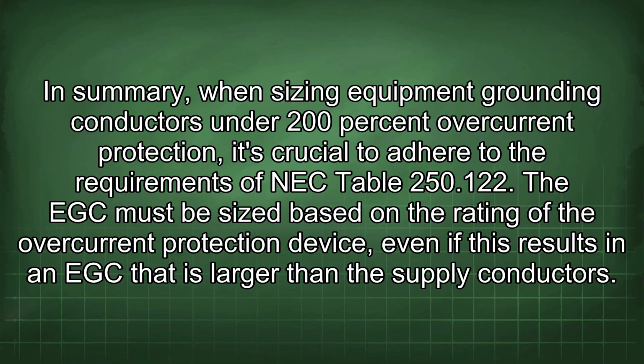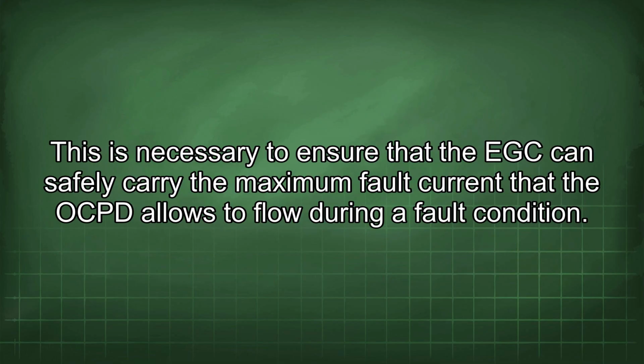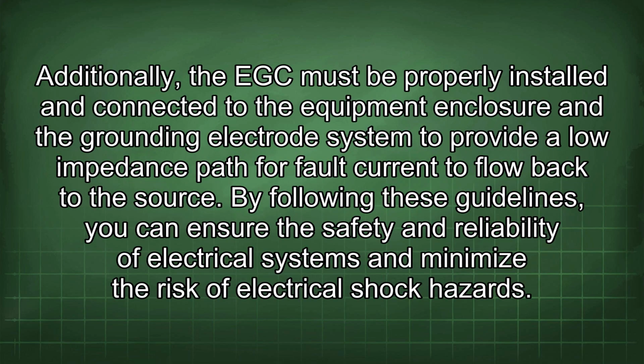In summary, when sizing equipment grounding conductors under 200% overcurrent protection, it's crucial to adhere to the requirements of NEC Table 250.122. The EGC must be sized based on the rating of the overcurrent protection device, even if this results in an EGC that is larger than the supply conductors. This is necessary to ensure that the EGC can safely carry the maximum fault current that the OCPD allows to flow during a fault condition. Additionally, the EGC must be properly installed and connected to the equipment enclosure and the grounding electrode system to provide a low impedance path for fault current to flow back to the source. By following these guidelines, you can ensure the safety and reliability of electrical systems and minimize the risk of electrical shock hazards.